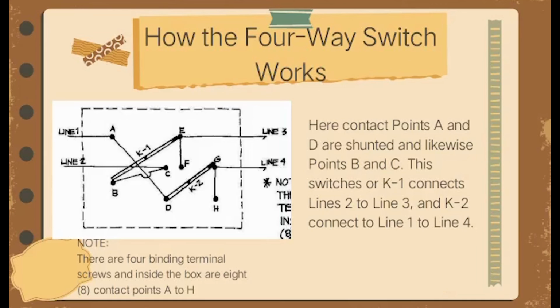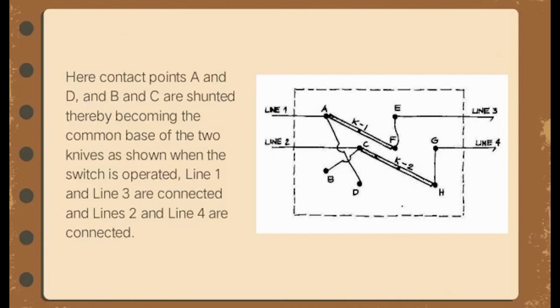Note that there are 4 binding terminal screws, and inside the box are 8 contact points, A to H. Here, contact points A and D and B and C are shunted, thereby becoming the common base of the two knives as shown when the switch is operated. Line 1 and line 3 are connected, and lines 2 and line 4 are connected.